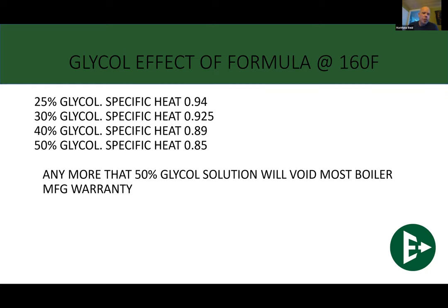And let's talk about this glycol percent solution. A lot of people use 50% glycol because they don't want their pipes to freeze and burst, and it's extremely common in snowmelt systems. But burst protection is not freeze protection. At 50% glycol, we get burst protection down to, I think, like minus 60 or minus 70. I've never seen that temperature anywhere in any of the southern provinces in Canada, ever. So why would we ever put a 50% glycol solution through that? Like here, as I said, I'm in Barrie, Ontario. The coldest temperatures we usually get are about minus 30. Now, 30% glycol gives me burst protection down to minus 35.